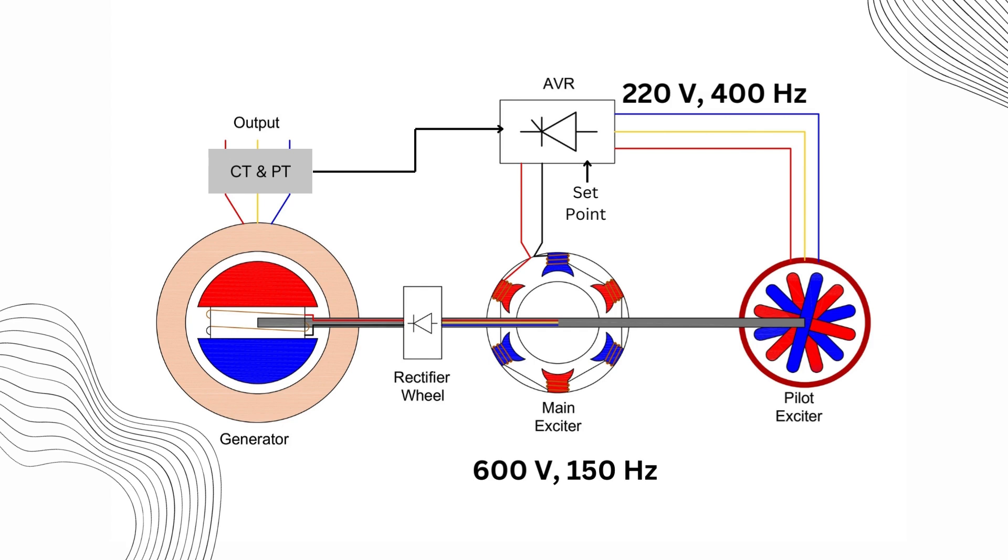Now measuring the rotor current directly isn't possible due to its location inside the rotating shaft. However, we can't just ignore this crucial measurement. To solve this, we use a quadrature axis coil mounted on the yoke of the main exciter. This coil indirectly measures the rotor current by inducing a proportionate voltage from the AC current flowing in the armature, allowing us to determine the rotor current.